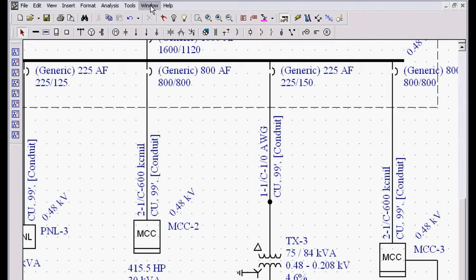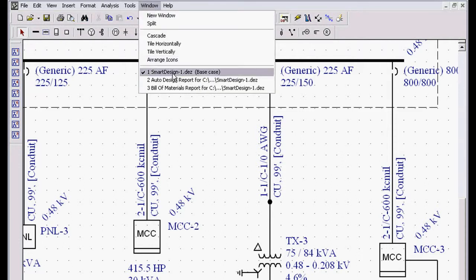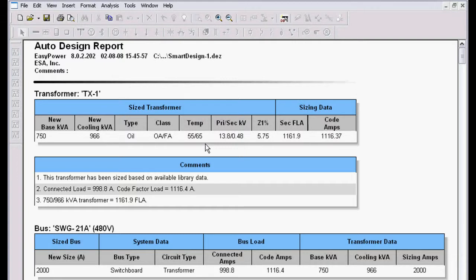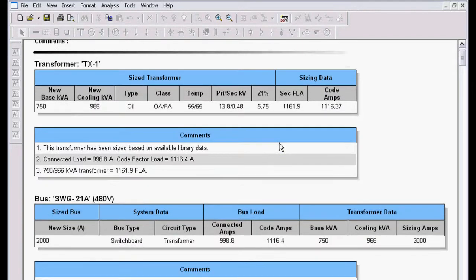If I go to window, auto design report, you can see that it gives me a detailed report of exactly what equipment it designed to, what were the design parameters, such as secondary full load amps, code factor amps, that type of information.